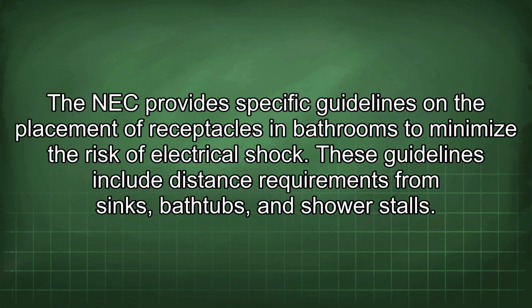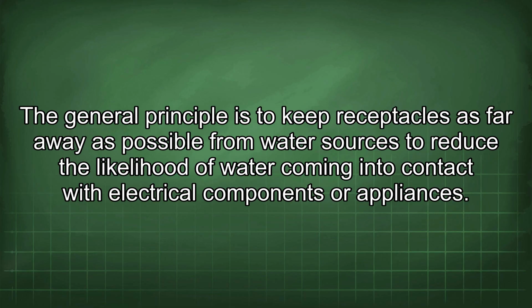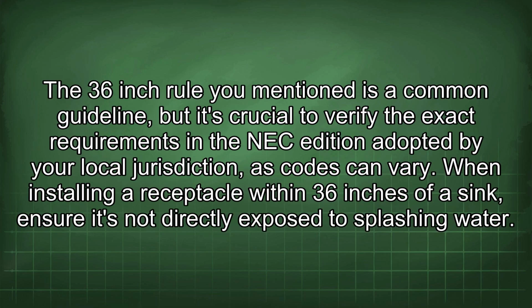The NEC provides specific guidelines on the placement of receptacles in bathrooms to minimize the risk of electrical shock. These guidelines include distance requirements from sinks, bathtubs, and shower stalls. The general principle is to keep receptacles as far away as possible from water sources to reduce the likelihood of water coming into contact with the electrical components or appliances. The 36-inch rule you mentioned is a common guideline, but it's crucial to verify the exact requirements in the NEC edition adopted by your local jurisdiction, as codes can vary.